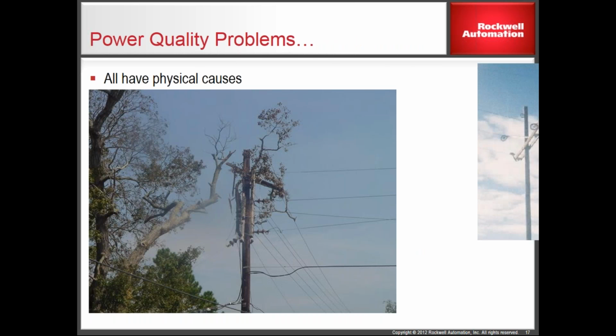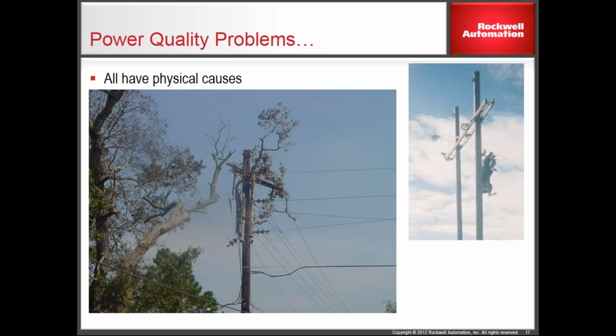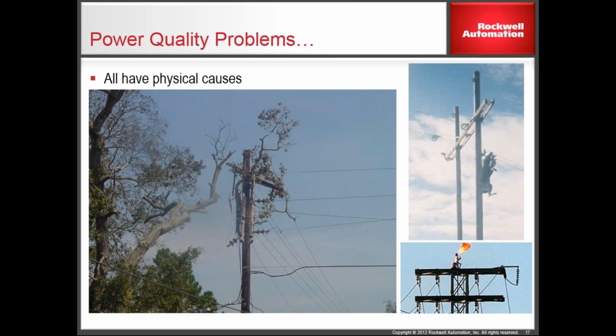Finally, the last piece I like to share, because sometimes power quality seems quite mysterious: at the end of the day, it's all traceable to some physical cause. It could be as simple as a loose wire in the outlet, chattering back and forth, or on the machine, and now you've got a power quality problem going on. In the grid world, 60% of the time it comes from weather, like a branch falling on a line, or a lightning storm that hits.